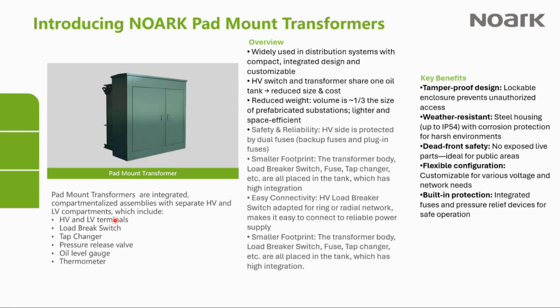customer use. So a pad mount transformer is fully integrated, both the HV and the LV compartments, and all the other components like the tap changers and the load break switch. All of these are integrated into one single unit, and that's what you have here. In terms of space saving, it's very fantastic because the volume is usually one third of a prefabricated substation. If you've ever seen a prefab substation, sometimes it could be in a 20-foot container, depending on the size of the transformer, and it's going to have the transformer inside, the MV switchgear, and the low voltage compartment, and usually it's very large, right?